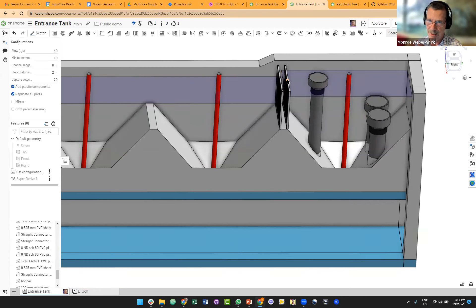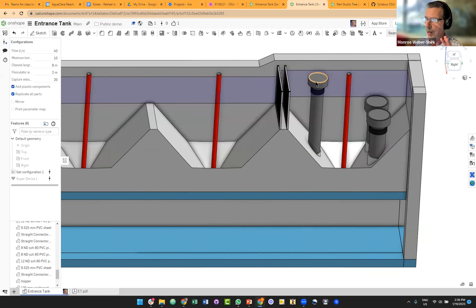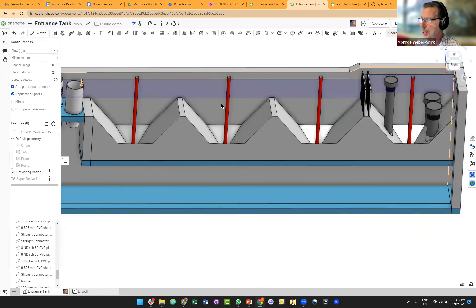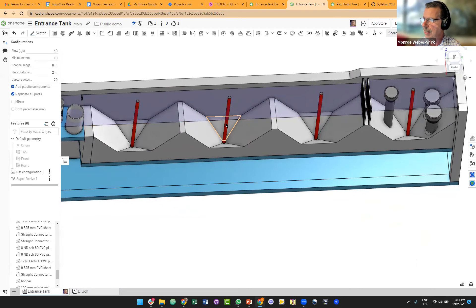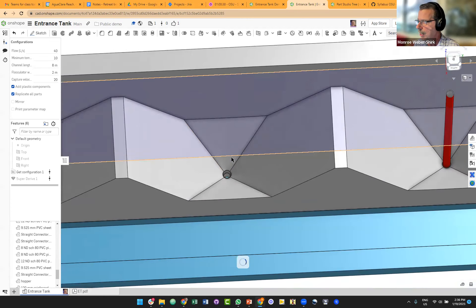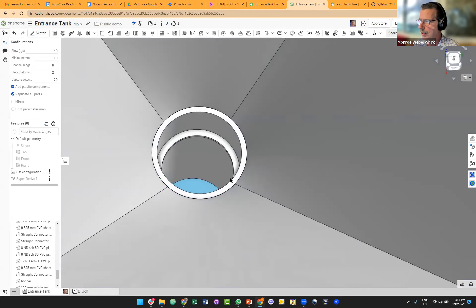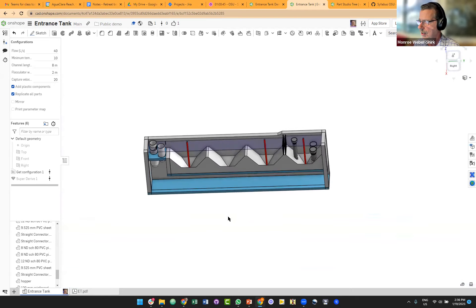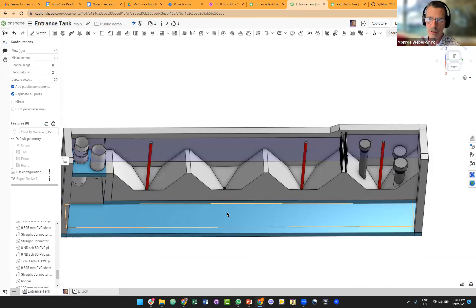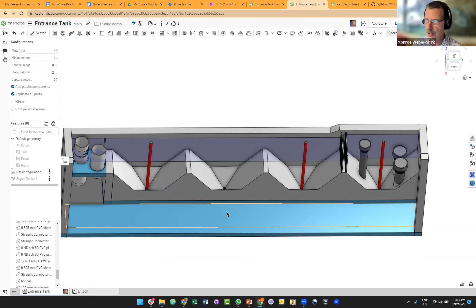This next pipe is used to dump water if the water level gets too high in the tank - if the operator forgets to clean the trash rack and the water level rises, it'll dump into the drain channel as an emergency overflow. These red pipes are the ones the operator can just grab and lift up. Let's remove one - it leaves a hole in the bottom of the tank that connects to the channel underneath. That's where the grit goes - sand that accumulates from the river settles in these hoppers.